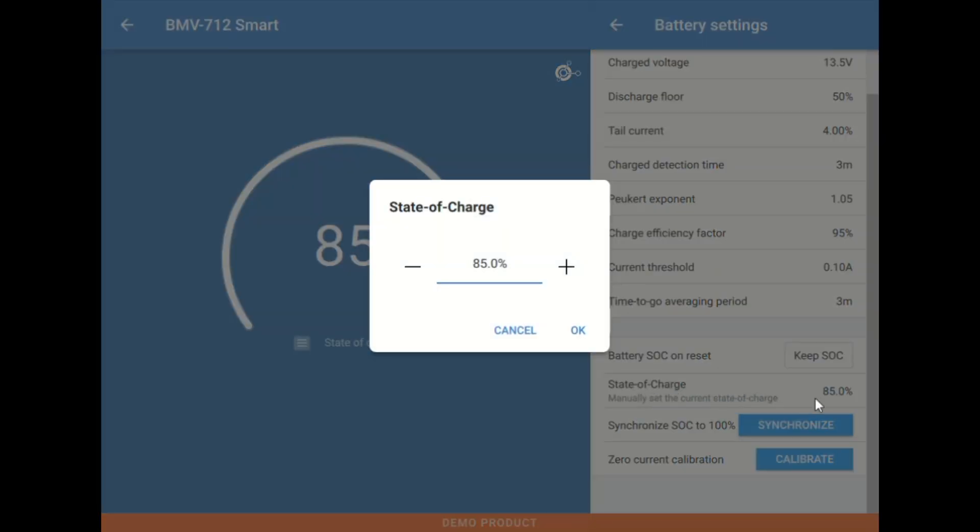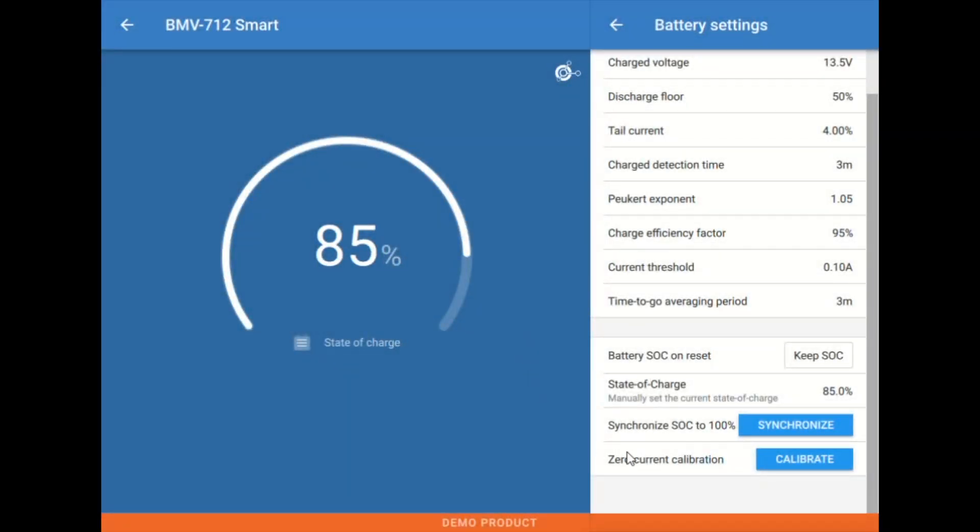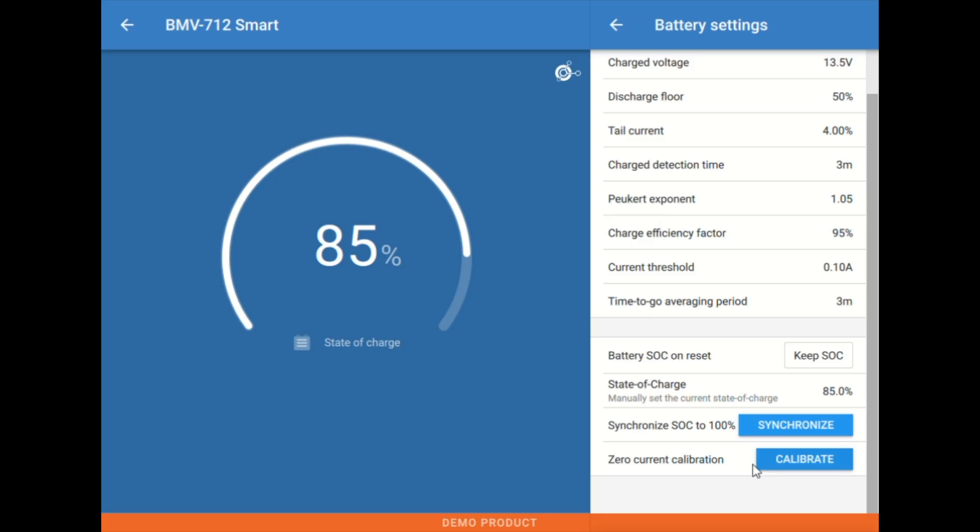This state of charge here is a place where we can set the percentage number manually. It's essentially what it seems like. It allows us to force the percentage to whatever given value we choose. Then we have a synchronized to 100%, which we may use on occasion if we know the batteries are full. And then this zero current calibration, which we almost never use unless there's some kind of issue, so I don't recommend using that.